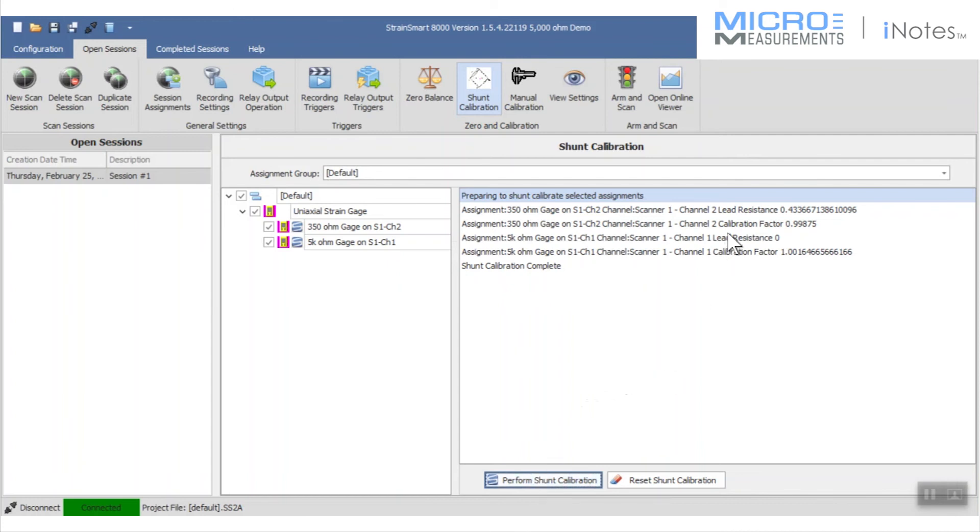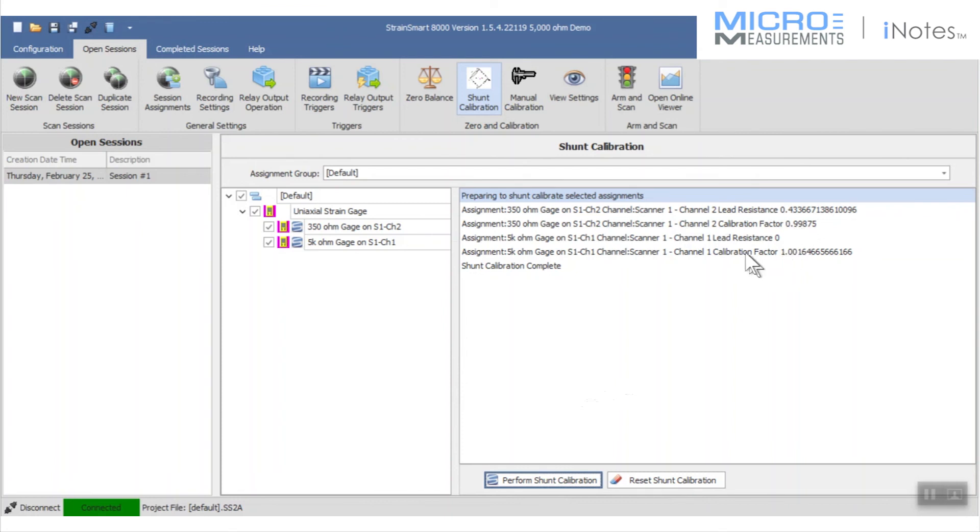Here it's saying it's finding a lead wire resistance in channel number two of about a half an ohm, so it's doing a slight correction to my gauge factor to correct for the lead wire resistance and the signal loss. We call that the modified gauge factor. The lead wire resistance found on the 5,000 ohm gauge, however, is really rounding off to basically zero, so it's not finding anything.